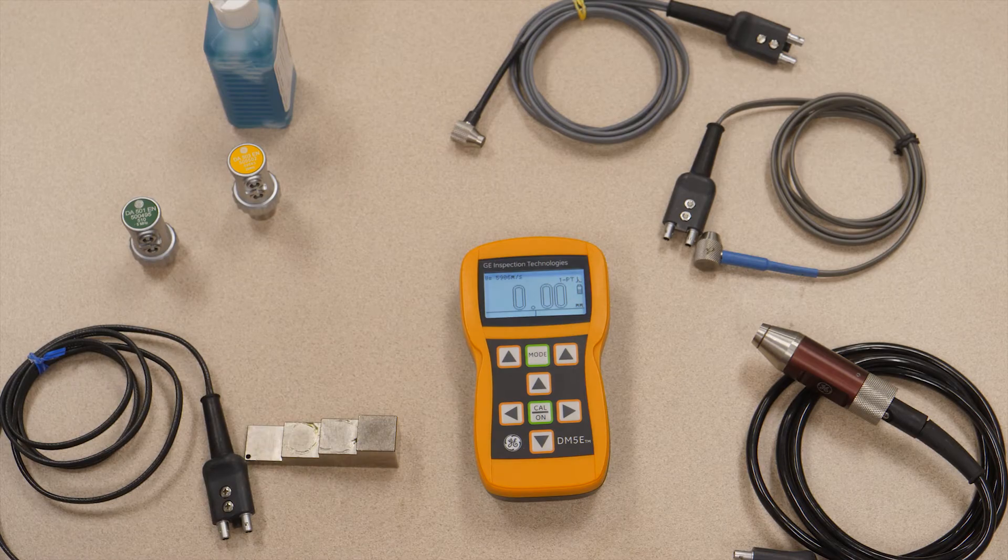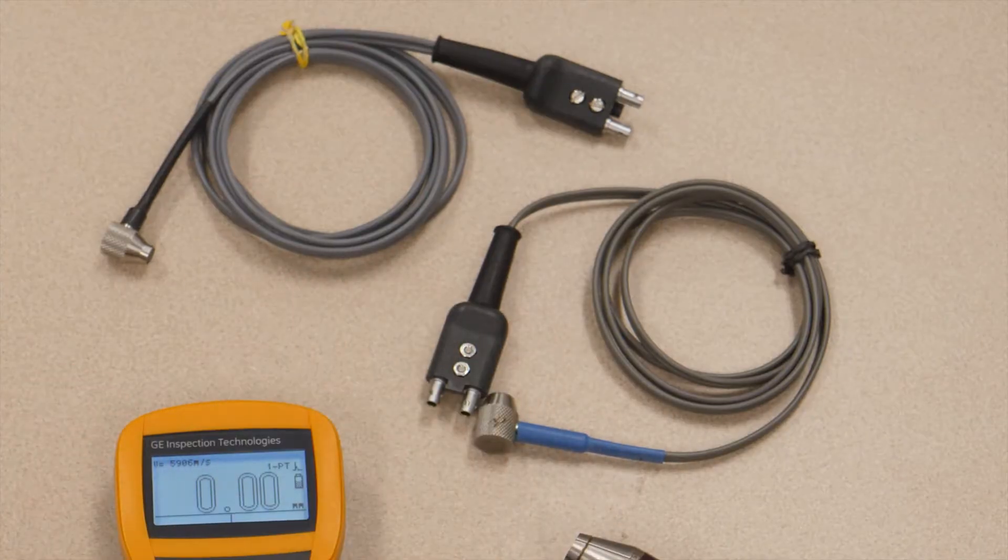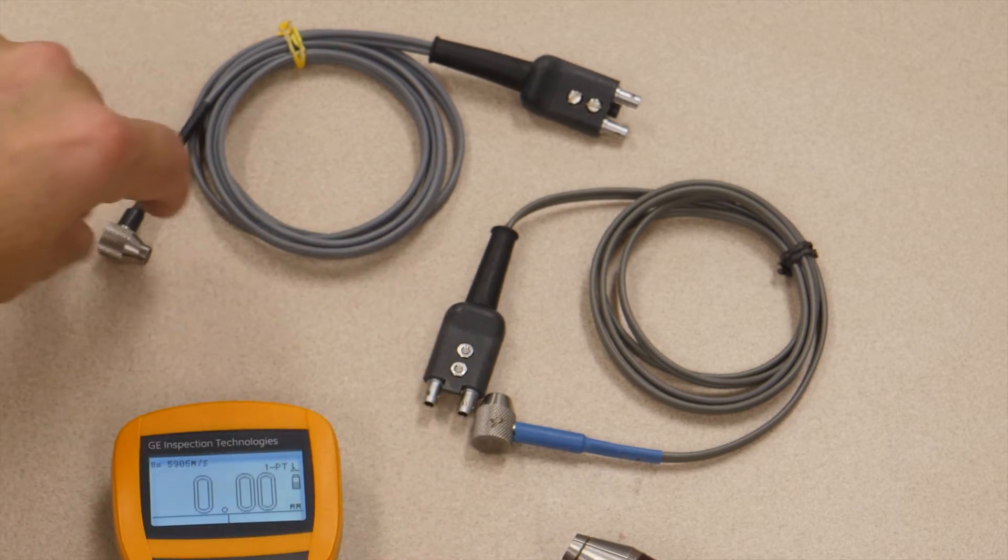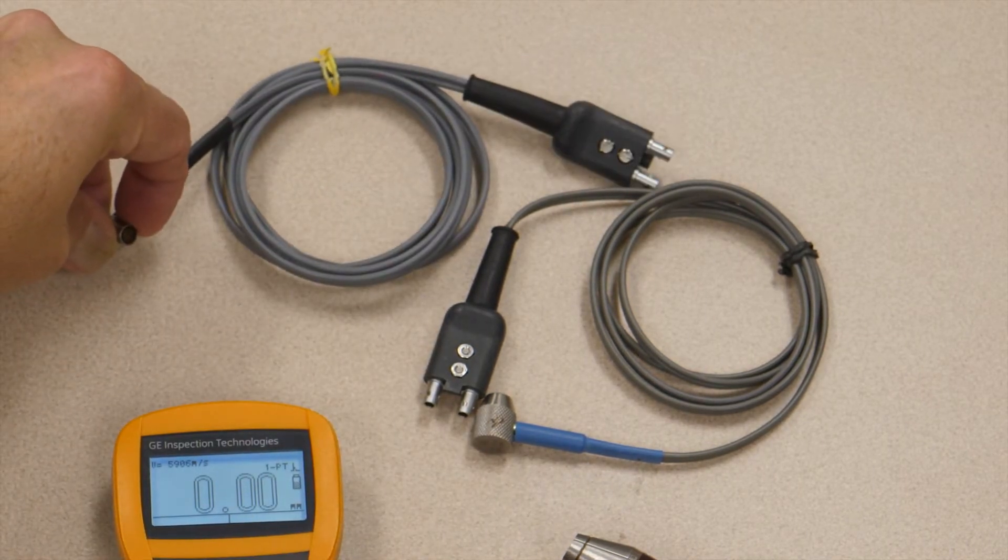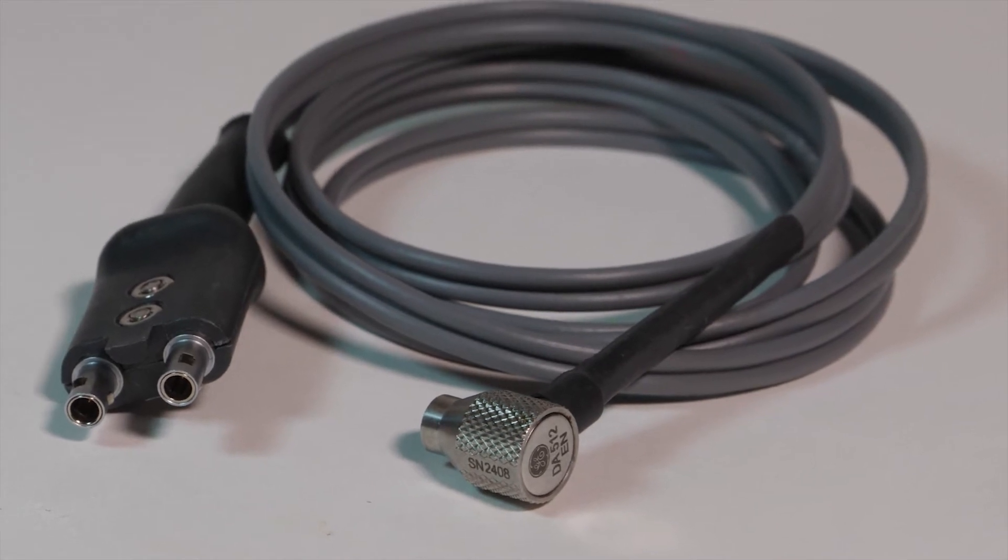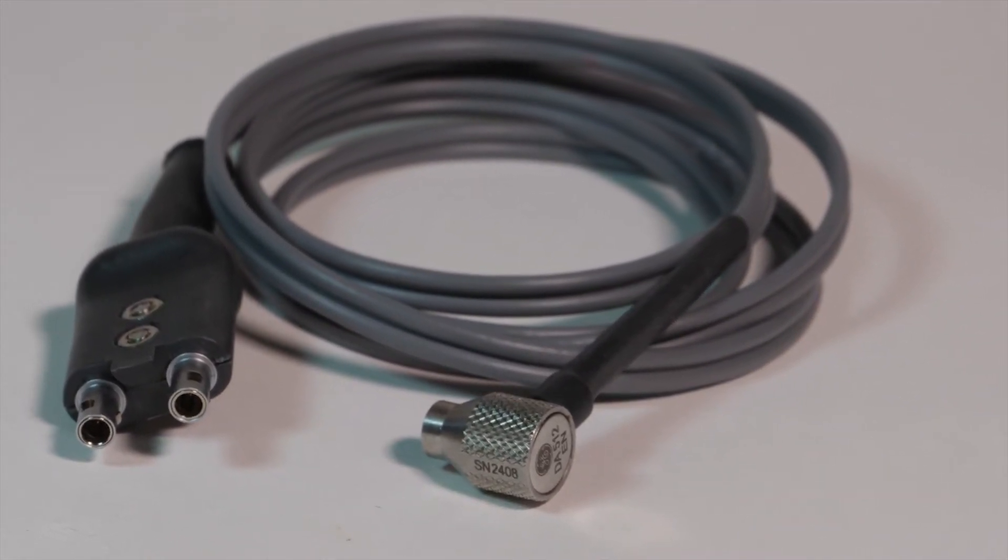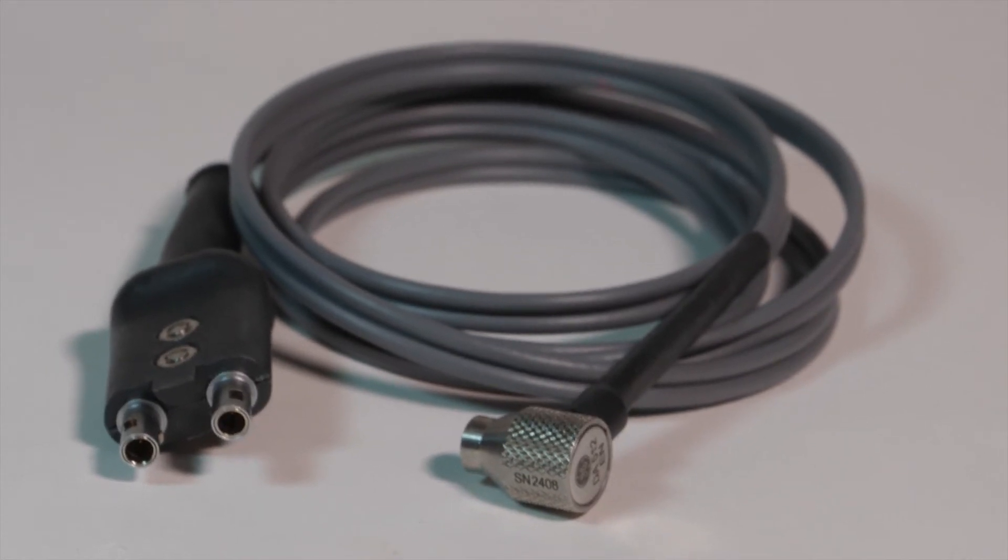So thicker materials, DA503. And we have our fingertip probes that are commonly used. The DA512 has a very small contact area, ideal for reaching into tight spaces and for reaching into pits on the surface of materials to take measurements of remaining wall thickness.